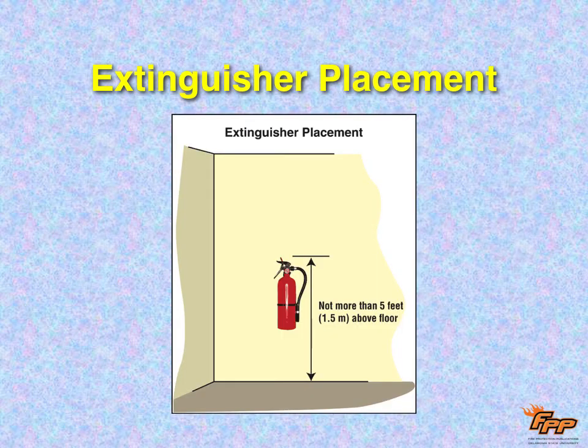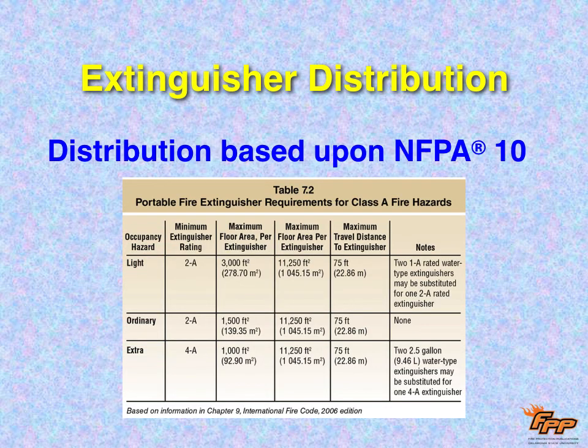Extinguishers should be placed 4 inches off the ground, no higher than 5 feet, unless they're higher in weight, then they're supposed to be a little bit further down. NFPA 10 tells us the spacing and distribution of fire extinguishers, at least 75 feet apart, for the most part, even if it's light, ordinary, or extra heavy fire hazards. 75 feet apart, and the ratings should be 2A, 4A, and the whole NFPA 10 will tell you all of those things.